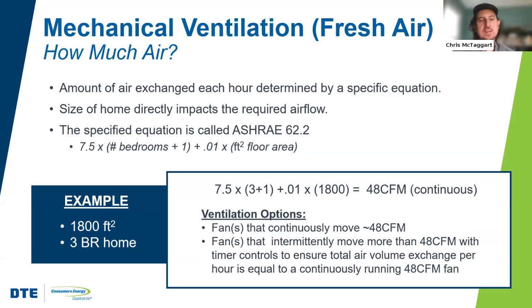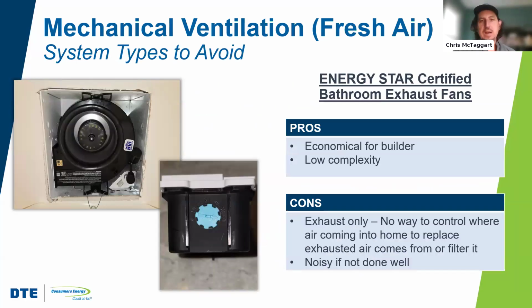as bedrooms plus one. So in this 1,800 square foot 3-bedroom home, you'd say 7.5 CFM times 4 people, because it's 3 bedrooms plus one. That would give us 30 CFM for the people, and then 1% of floor area gives us 48 CFM total. That would be continuous. That would mean that you'd either have one fan running continuously at 48 CFM, or you would have one that is set up to run at a higher rate, but on a reduced runtime schedule. If you're going to use exhaust-only ventilation, then you have to have them set up as Energy Star bath fans.